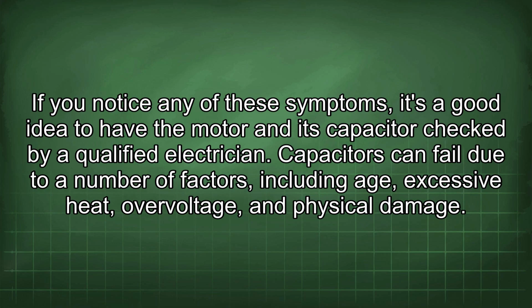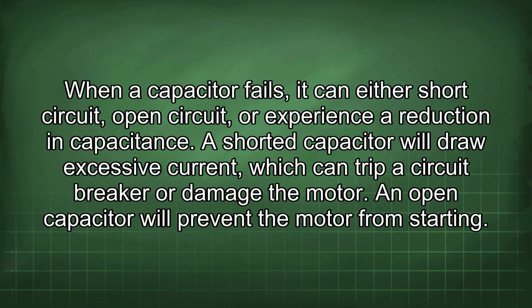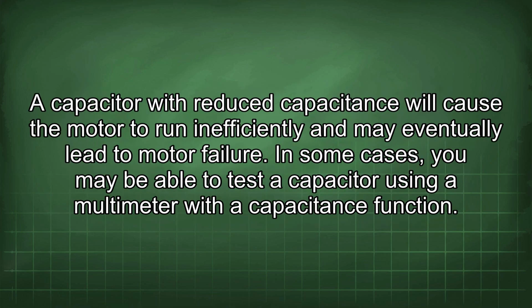Capacitors can fail due to a number of factors, including age, excessive heat, overvoltage, and physical damage. When a capacitor fails, it can either short circuit, open circuit, or experience a reduction in capacitance. A shorted capacitor will draw excessive current, which can trip a circuit breaker or damage the motor. An open capacitor will prevent the motor from starting. A capacitor with reduced capacitance will cause the motor to run inefficiently and may eventually lead to motor failure.